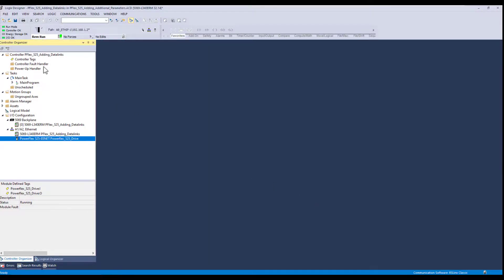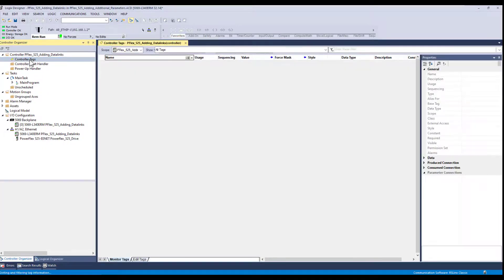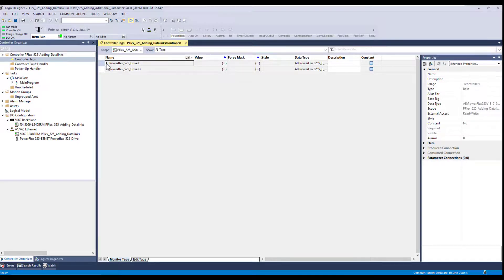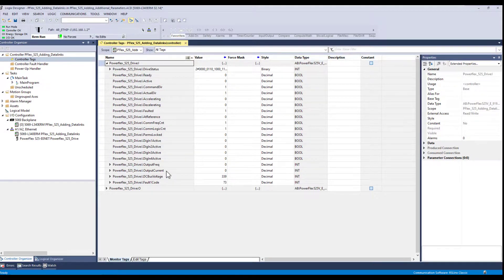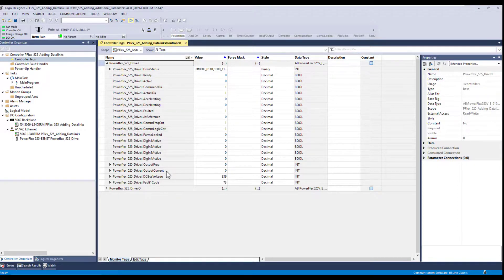Now let's go take a look at the controller tags and see that information updated in here. So again, this is the input information from the drive to the PLC. So if we look at this, we can now scroll down to the bottom and now you'll see the output current, bus voltage, and fault code being fed from the drive back into the PLC.